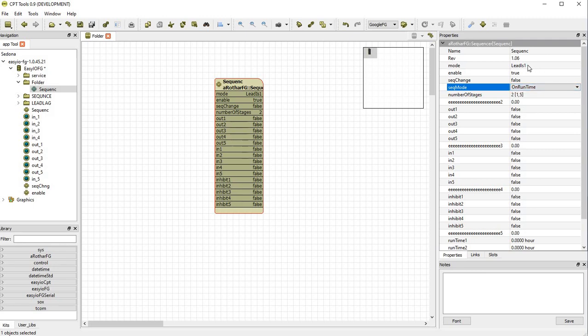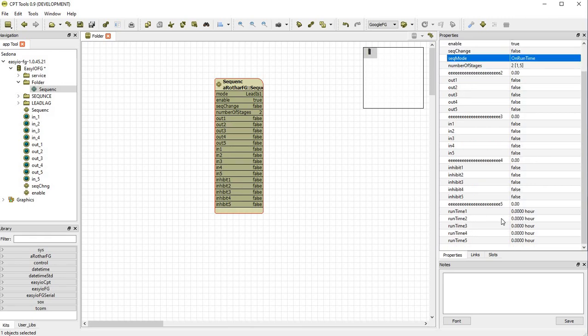The mode will tell you which one is currently leading. The block also offers a sequence change one-shot input and some fault inhibit control. The block will also manage its own internal runtime. Now this is based on the output being turned on, so it's more a command rather than a status driven runtime.